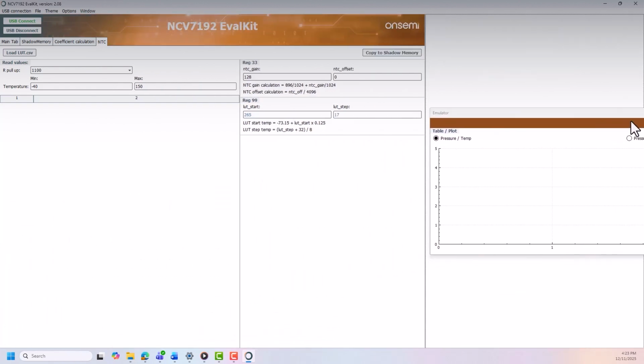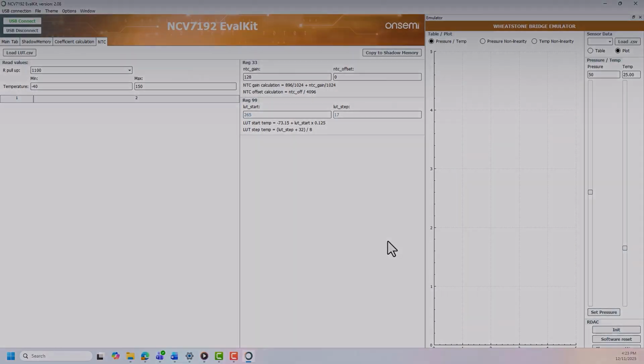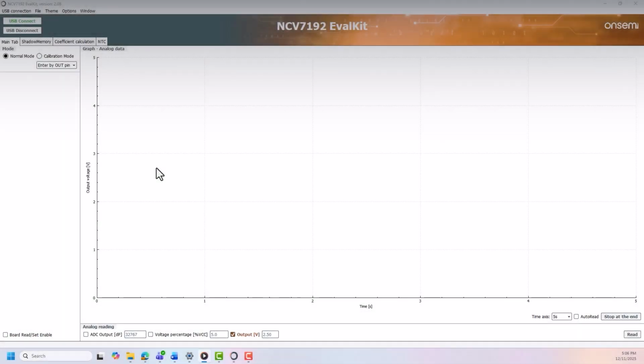Now I'll show you how you can perform bridge sensor calibration using the Evaluation Kit and Wheatstone Bridge emulator, which will emulate pressure signal. Let's assume that we have fresh unprogrammed device. I will not go into details about math behind the calibration. You can read it in NCV7192 configuration and calibration application note. I'm starting from normal mode. USB is connected. Let's open emulator window.